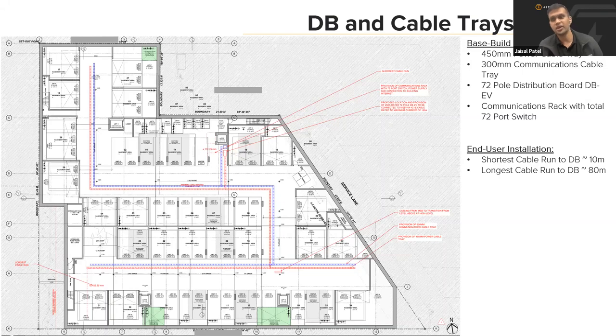Sorry, I saw a question earlier, but I'll get back to that one. So 300 mil communications cable tray, we size that based on a 6.1 millimeter diameter of a Cat 6 cable. We allow for a 72 pole off-the-shelf MCB distribution board for EV charging and a communications rack with a total of 72 ports in it for each EV charger plus a few spares. Next slide.